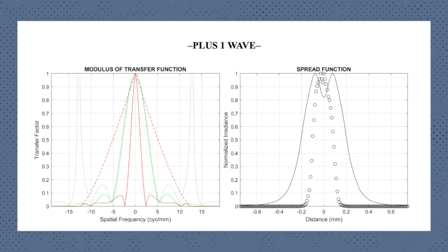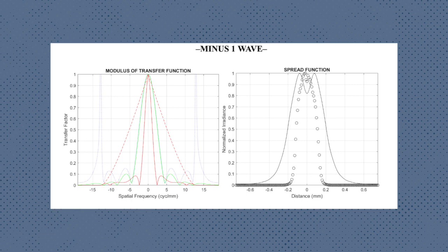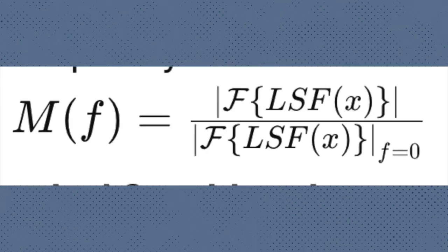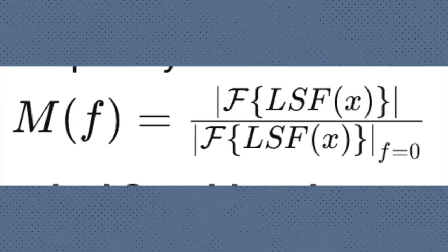On the right, we compare our experimental LSF to our theoretical LSF. In all cases, our experimental is pretty close to our theoretical values. Behind the scenes, we are actually taking the Fourier transformation of the LSF function and then normalizing that Fourier transformation of the LSF with the Fourier transformation of the LSF at the 0 frequency.